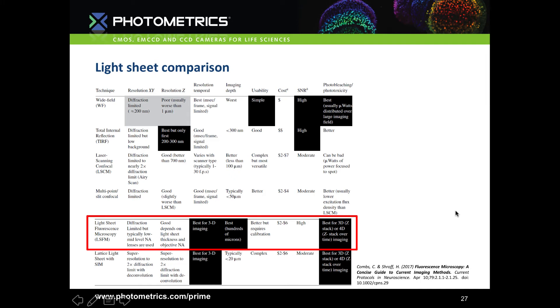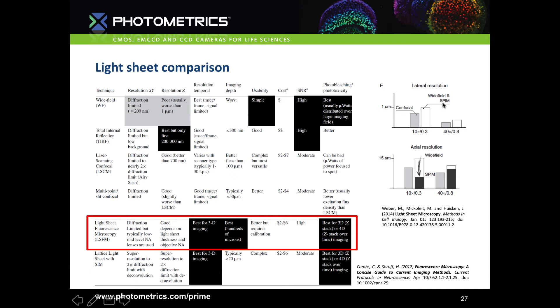This comparison chart by Hari Shroff compares lightsheet fluorescence microscopy against widefield, TIRF and confocal. In terms of temporal resolution and imaging depth, lightsheet is considered best for 3D imaging. For photobleaching and toxicity it's best for 3D and 4D imaging, with a high signal-to-noise ratio. It's still diffraction-limited but Z-resolution is comparable to confocal. Using a 10x objective, lightsheet gives about twice the axial resolution of confocal; even at 40x, lightsheet still offers huge improvements in photobleaching and phototoxicity.